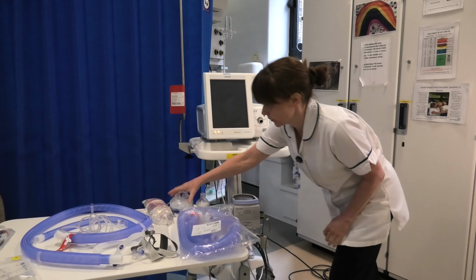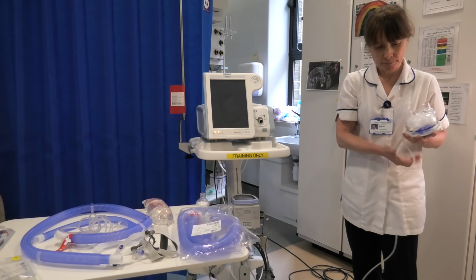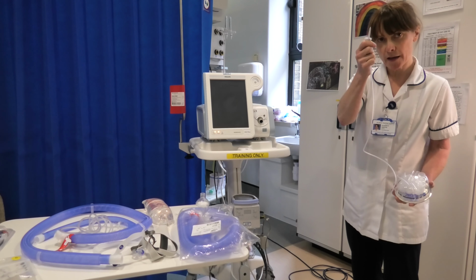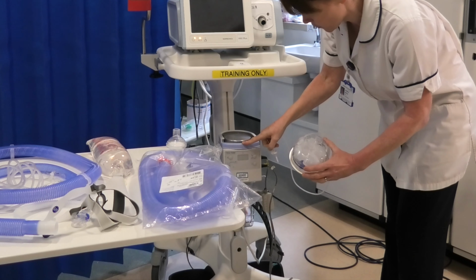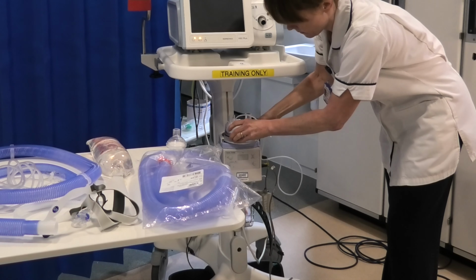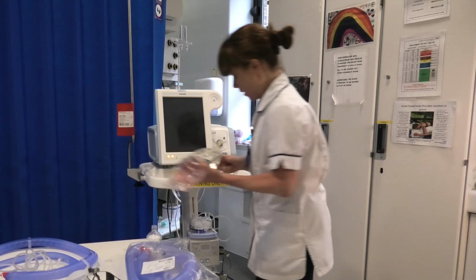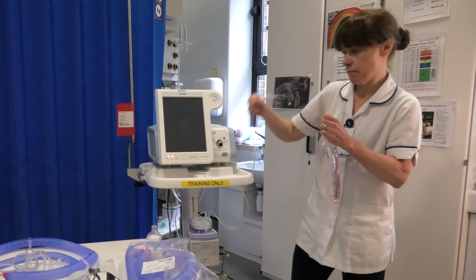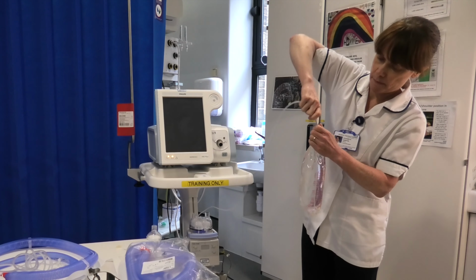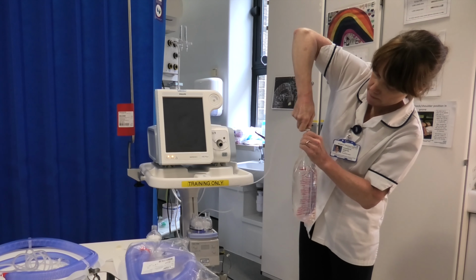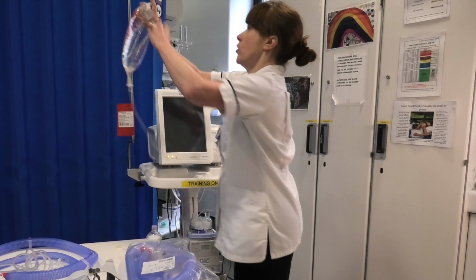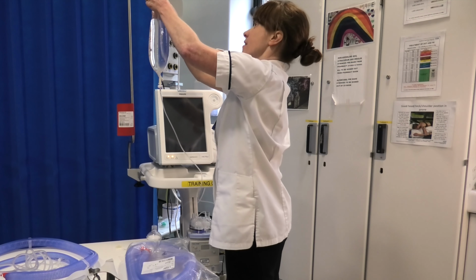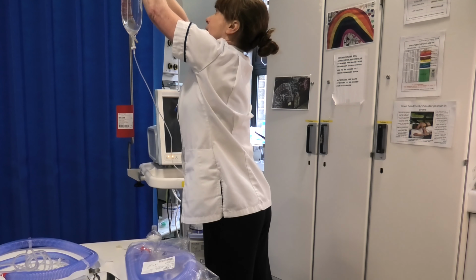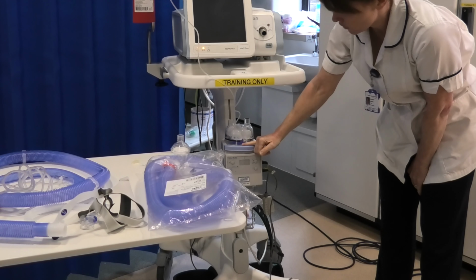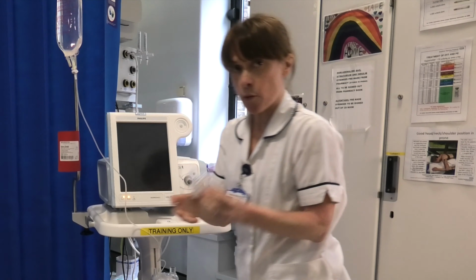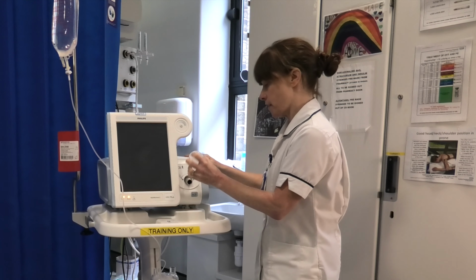So we need a chamber with an entrainer, which we put a bag of sterile water. So to put that in, you push the front of the humidifier down and slide it in. Use a bag of sterile water. Push that in, hang it up on the hook, and that feeds the ventilator, feeds the chamber. So you get sterile water filling this chamber. We need a separate filter. The filter goes onto the ventilator.